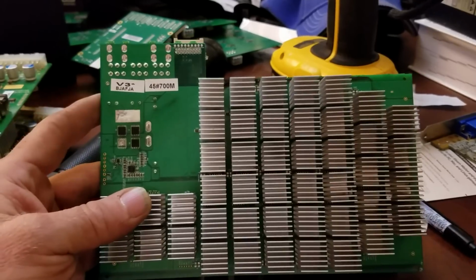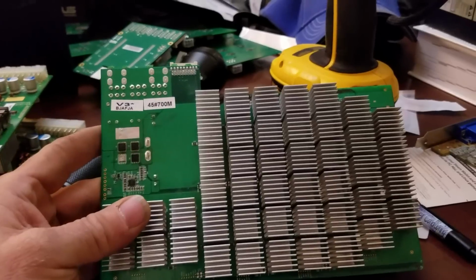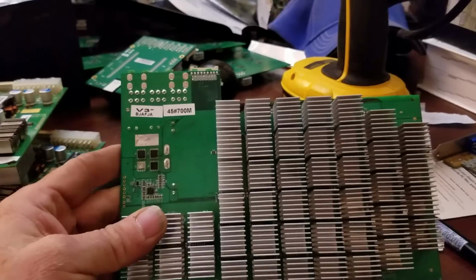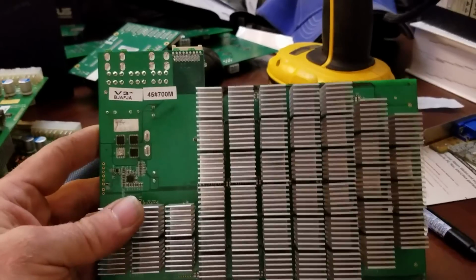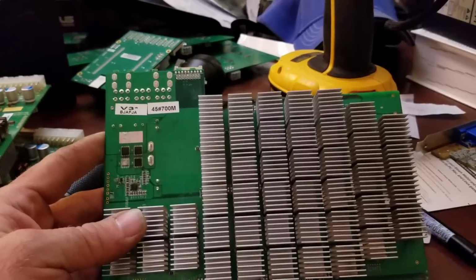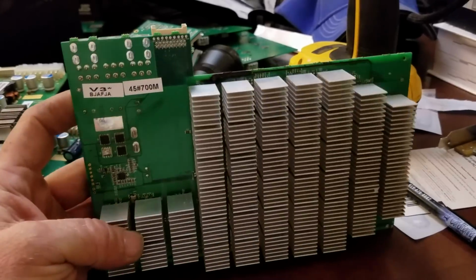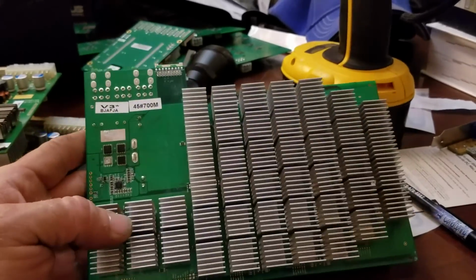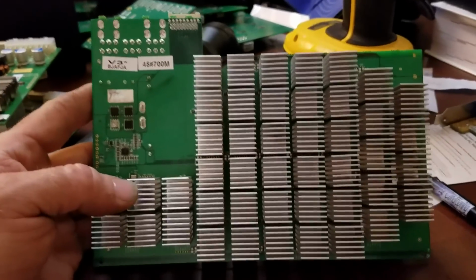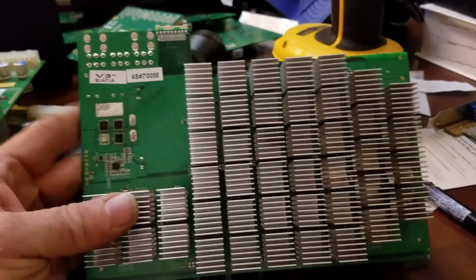Well, it could be that some of the components begin to overheat over a very slow period, due to, let's say, a dirty filter that causes high static pressure, or something that is causing the slow rise in temperature of this board. The most common thing that I have talked to people about is airflow. Airflow and static pressure are the two most important things when you're talking about maintaining the longevity of these boards.